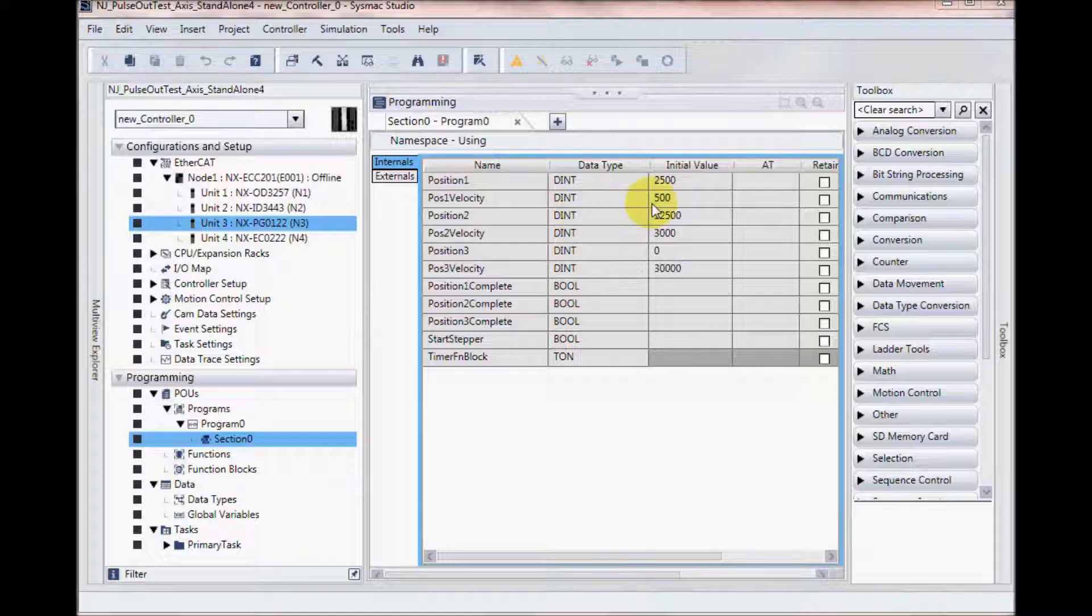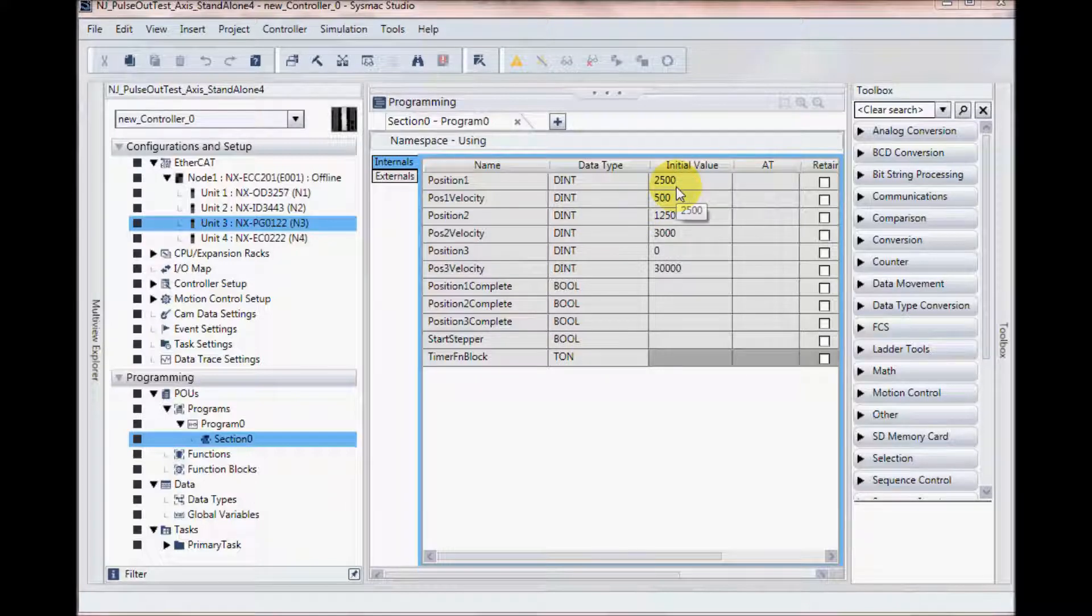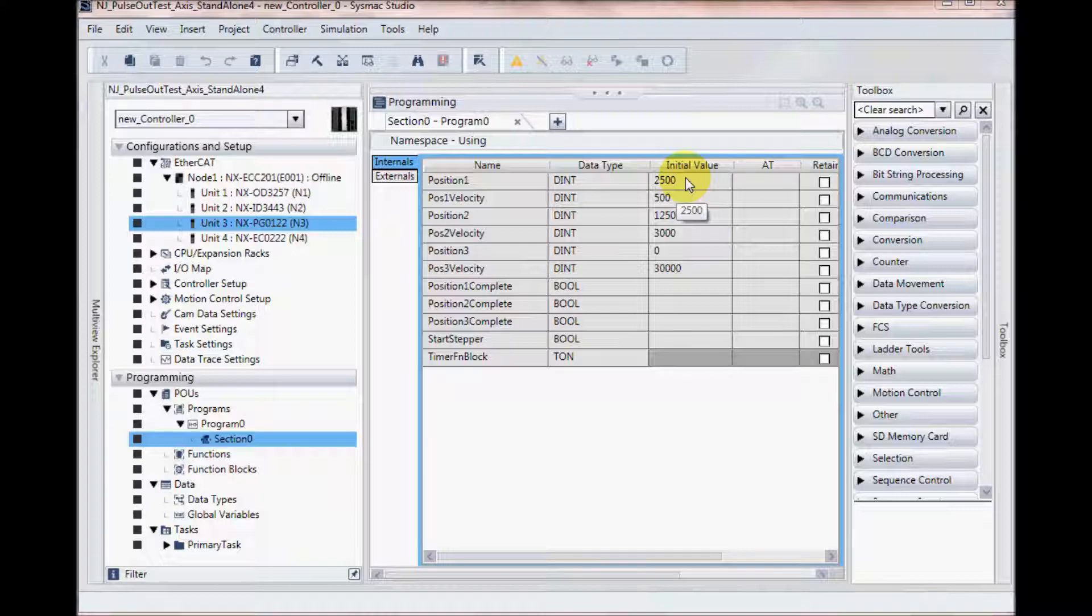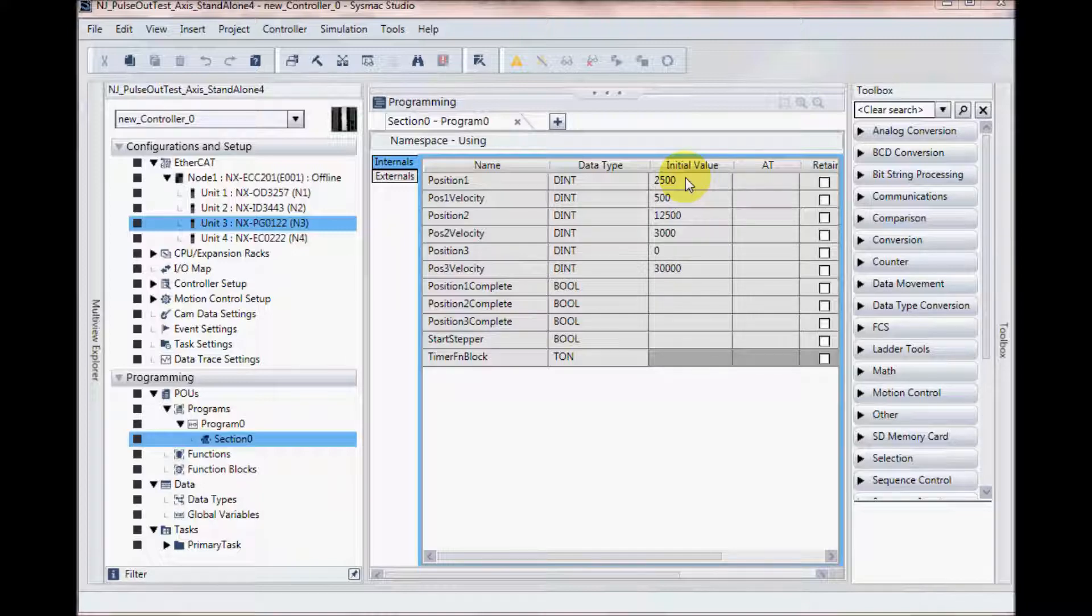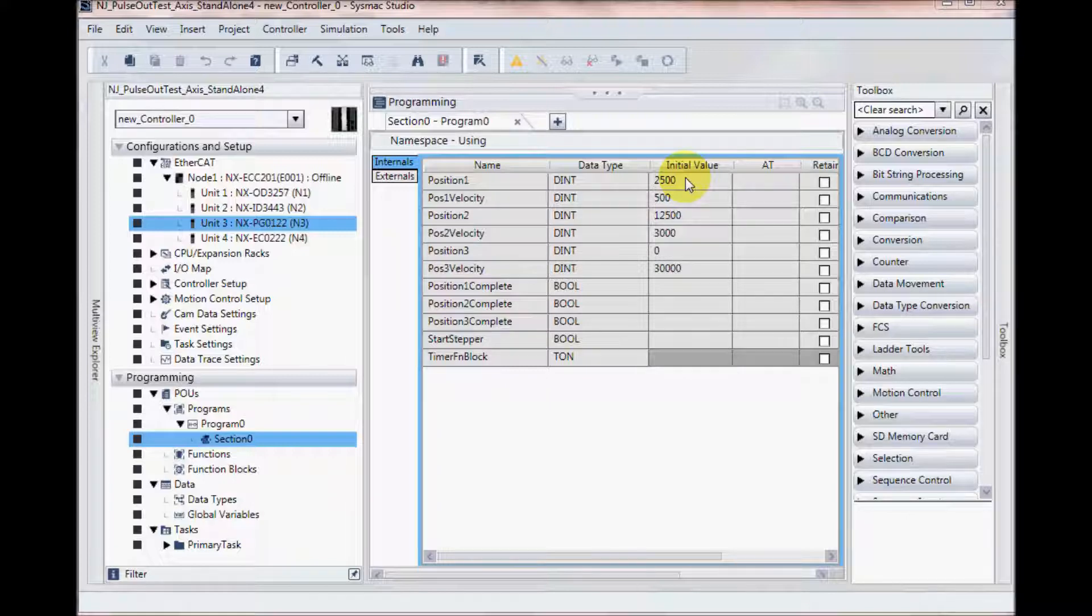You will notice here I have set some initial values. So my position 1 is set for 2,500, and that would relate to one revolution on the motor that I have selected. It's a 2,500 pulse per revolution motor. My first velocity is going to be 500 pulses per second.